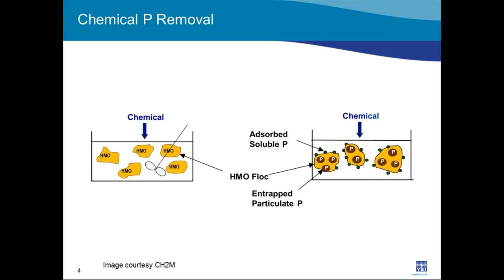The first application is chemical phosphorus removal. It's a fairly simple process that involves adding chemical to the water, forming flocs called HMOs — hydrous metal oxides. As these flocs are formed, soluble P adsorbs to them, and then particulate P gets trapped as the flocs continue to grow. When these flocs settle out, they are removed with waste sludge.